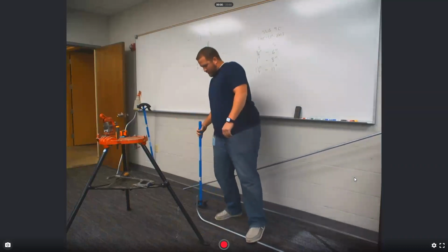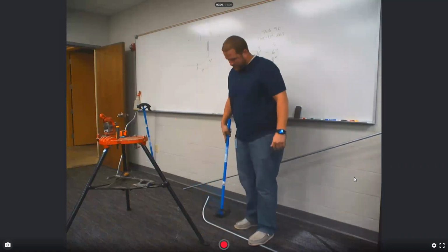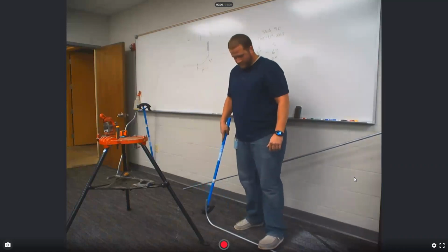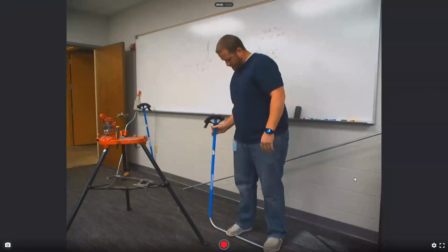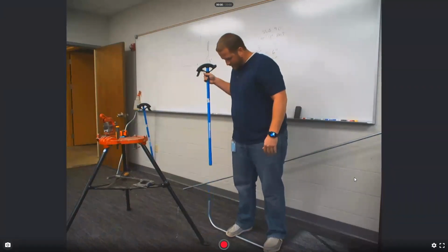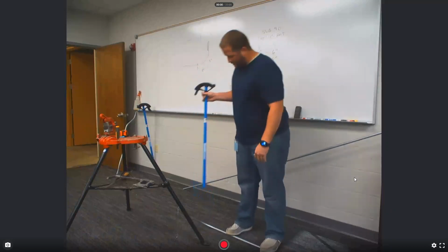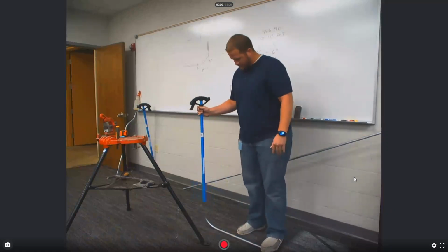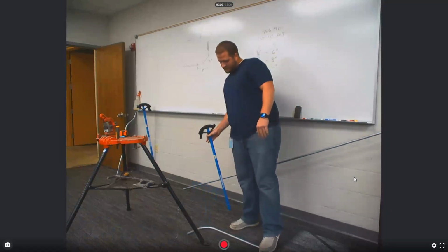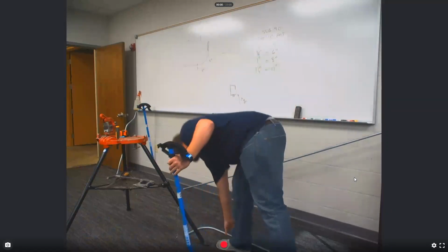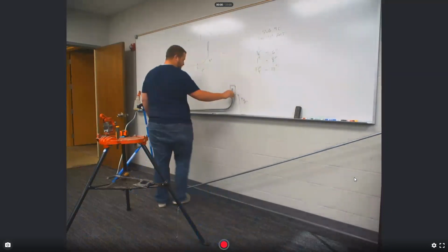I actually overbent that a little bit. Can you see that? The good thing about half-inch EMT is that it's really easy to fix that. And how you fix that is put it in there and go. Pretty good? It's still a little overbent to me. It's better. And if we did that right, it should fit right at the bottom of that coupling.